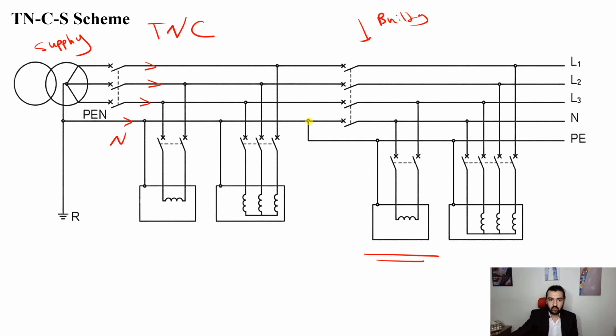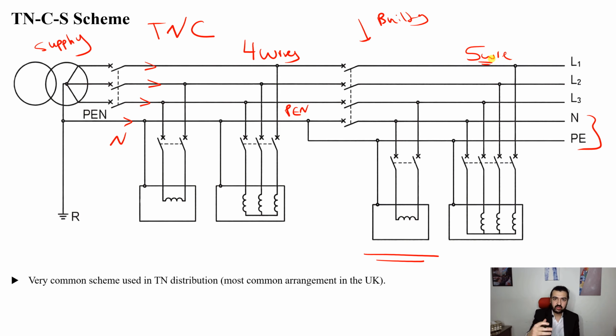In that building, we are going to start. So we have PEN. I'm going to start to separate it into 2 wires, neutral and protective earth. So the PEN is divided into neutral and protective earth, as you can see here, converting it from a 4-wire system into a 5-wire system. Now this one is acceptable, and you can find this arrangement commonly used in the UK.